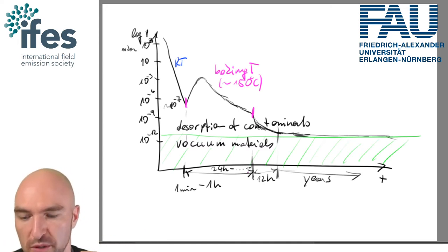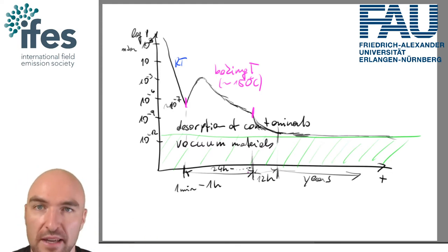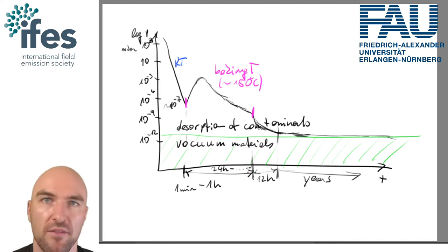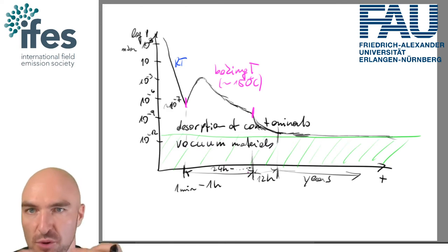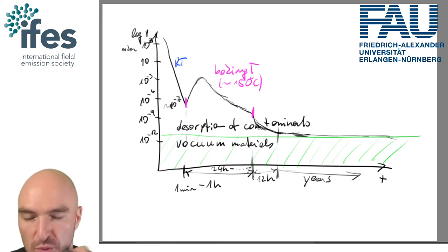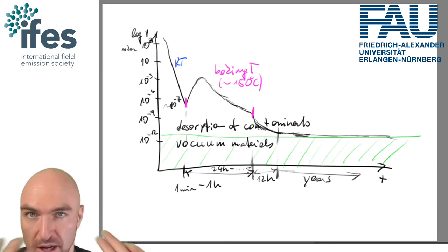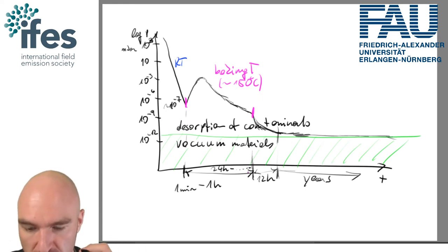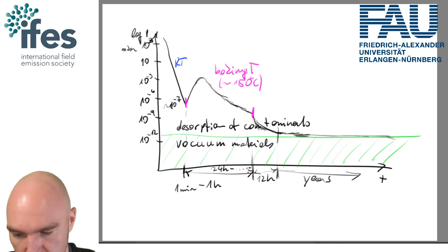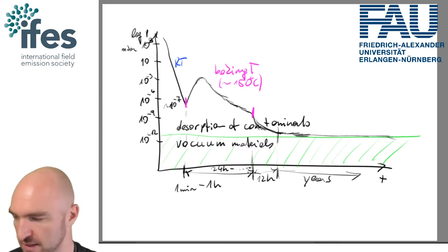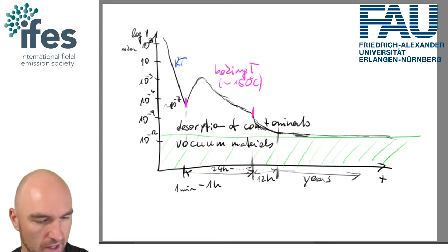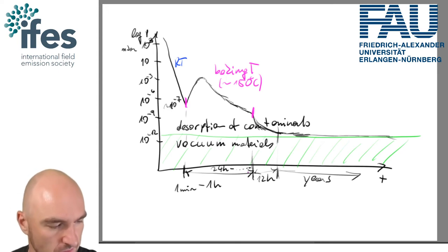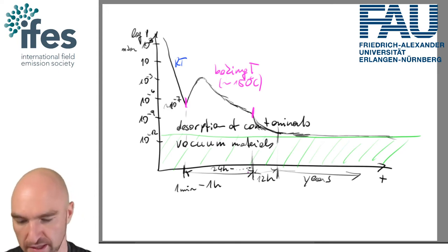And in atom probe tomography, we have a thermally insulated stage. So usually it's a good idea to bake for 36 hours. We, for example, have ultra high vacuum coating systems where everything is thermally well connected. There you only need to bake for 24 hours or maybe even 12 hours, and the whole system will get evenly warm. And it depends on what contaminants you have. But this is roughly the baking schedule that you would have, and this actually gets you to ultra high vacuum.